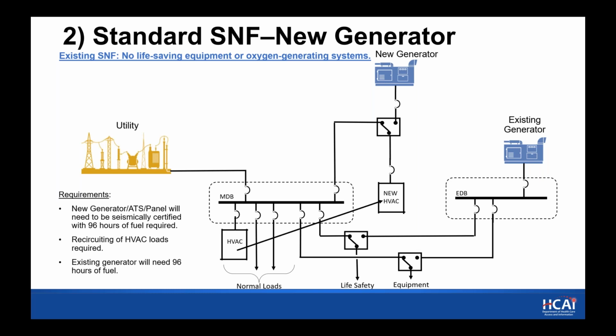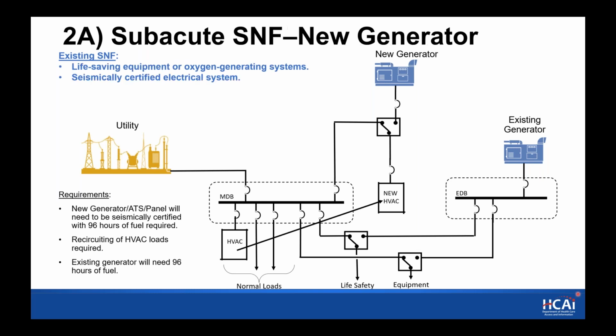And now I want to make a distinction, and I'll revise that slide, but essentially, if you have an existing SNF and there's no life-saving equipment or oxygen generating systems, then your existing generator with nominally 6 hours of fuel could remain as is, and you would only need to address the fuel for your new generator. That would meet the requirements of this bill.